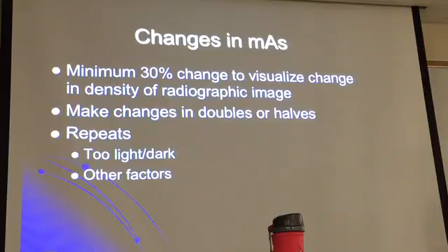Okay? So, Ashley Valentino, Ethel Cruz, Rachel Kreider, Hilda, if you apply the 15% rule in KVP, you increase it by 15%, that will be the same as doubling your density, doubling the mAs. Make sense? Okay, that will be the same.